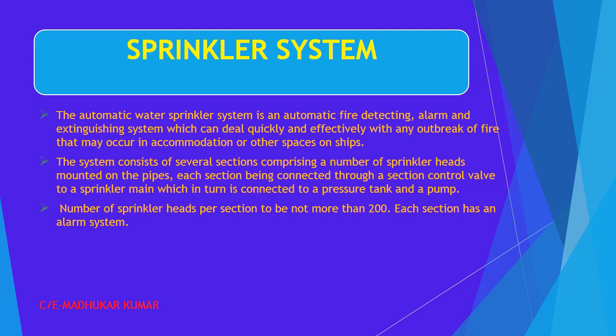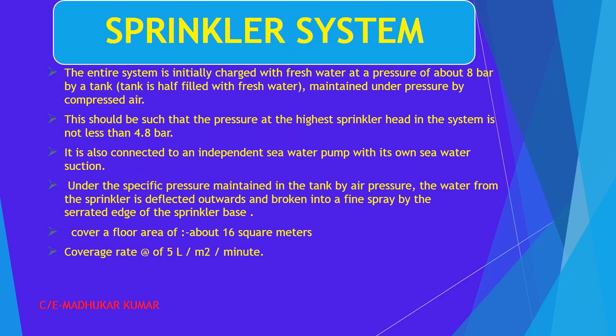And for each section, the maximum number of heads which can be installed is 200, and each section also has an alarm associated with it. Okay, the entire system is initially charged with fresh water, at a pressure of 8 bar, by the tank which is half filled with fresh water, and on top you have the air arrangement. It is maintained under pressure by the compressed air. This should be such that the pressure at the highest sprinkler head in the system is not less than 4.8 bar. This is the system requirement.